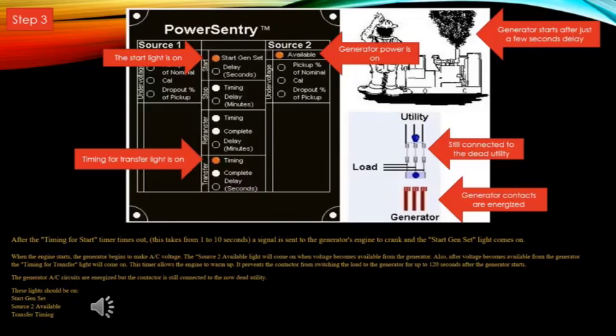It prevents the contactor from switching the load to the generator for up to 120 seconds after the generator starts. The generator AC circuits are energized, but the contactor is still connected to the dead utility. The start light is on, the timing for transfer light is on, and the generator power available light is on. You can see smoke coming out of the generator stack indicating the generator is running. The contactor is still connected to the utility, and the generator contacts are energized — shown in red.